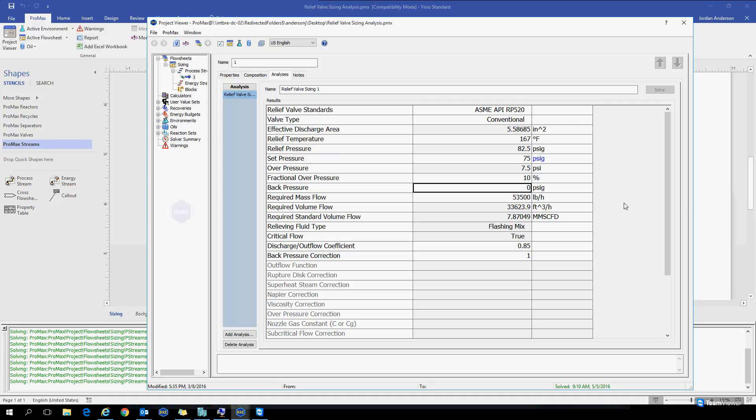The next variable we see here is our back pressure, which oftentimes might be close to atmospheric pressure if you're leading to the atmosphere. But if you have a long line of tubes or you're going on to another process, this back pressure might be higher and that might be something you need to calculate.